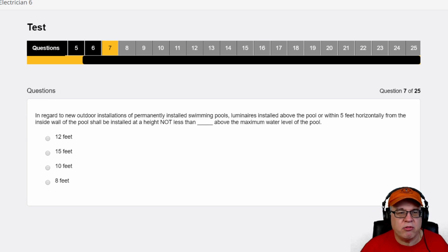Let's do the next one. In regards to new outdoor installations of permanently installed swimming pools, luminaires installed above the pool or within 5 feet horizontally from the inside wall of the pool shall be installed at a height not less than blank above the maximum water level of the pool. Now, I serve on that code making panel, so this one's pretty easy for me. But one thing's for sure, it tells me where I've got to be. Right now, I know I'm in swimming pools.